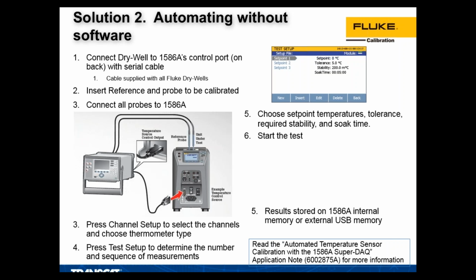I also determine the tolerance I'll accept on that set point—for example, within a degree, a tenth of a degree, or even a hundredth of a degree. It won't take data until it's inside the tolerance, until it meets the stability criteria set on this screen, and until the soak time I've set has completed if I want to ensure it waits a certain period. Those are unique features of automating with the 1586.